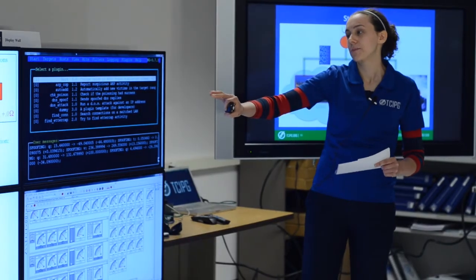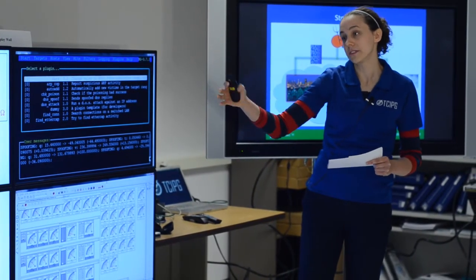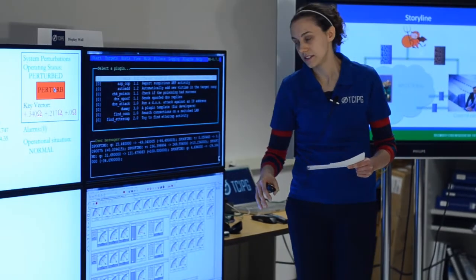And so we're affecting changes in complex impedance on these three lines here that are highlighted in blue. And so now that we've affected the perturbation, we see the new measurements coming in. And we compare them to what we expected to see.